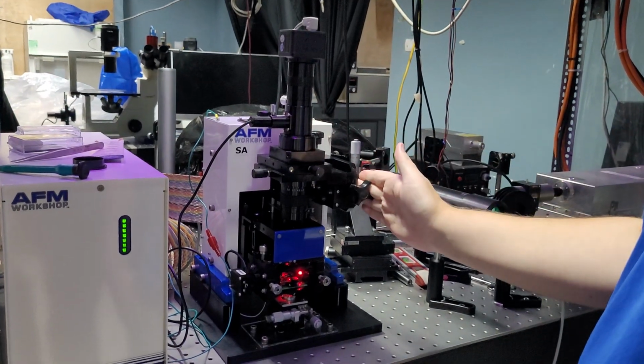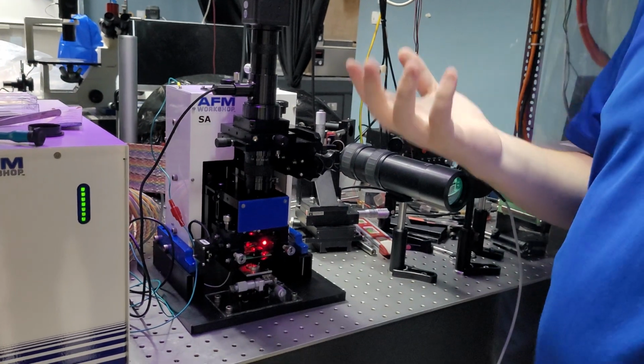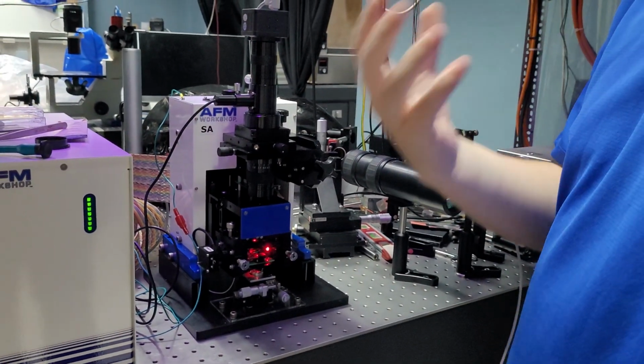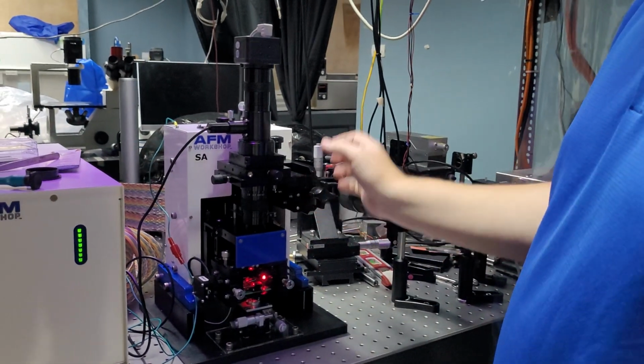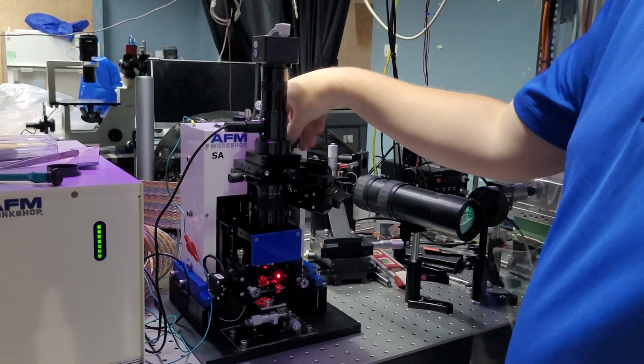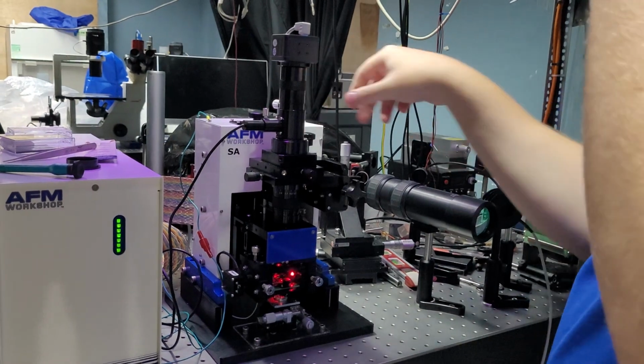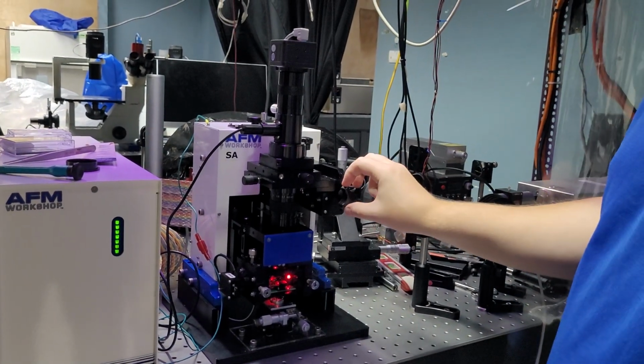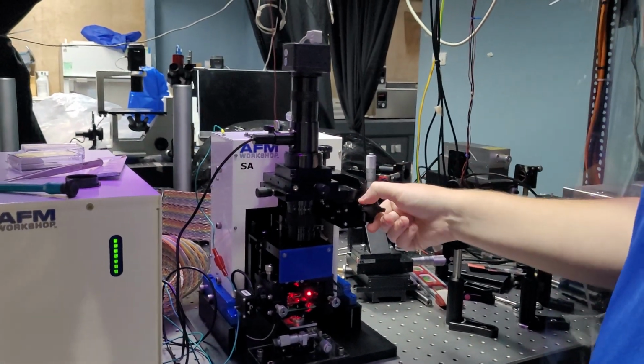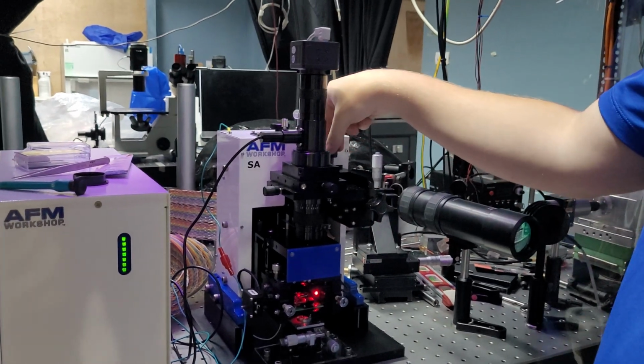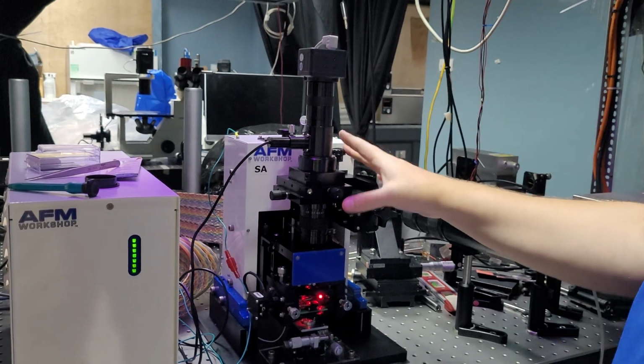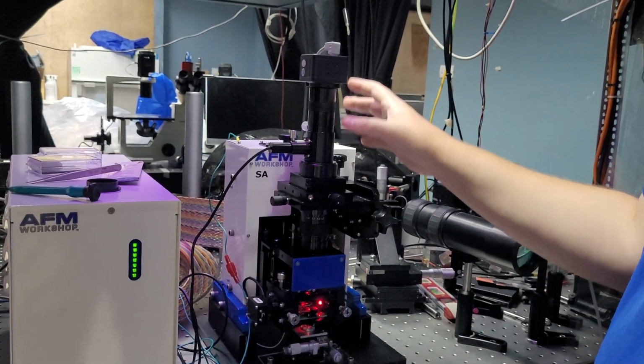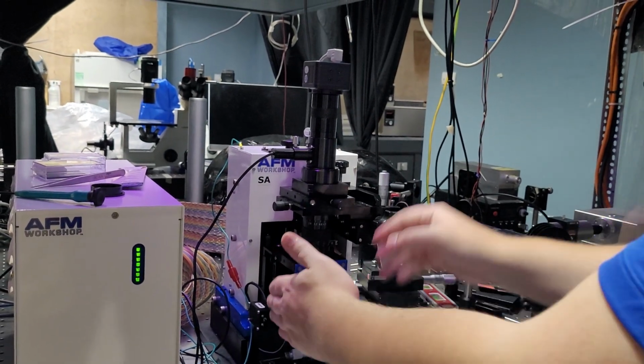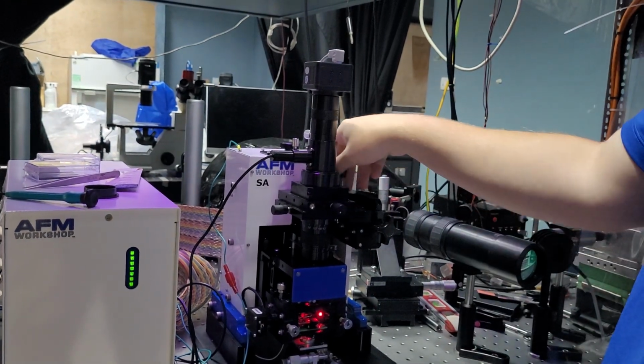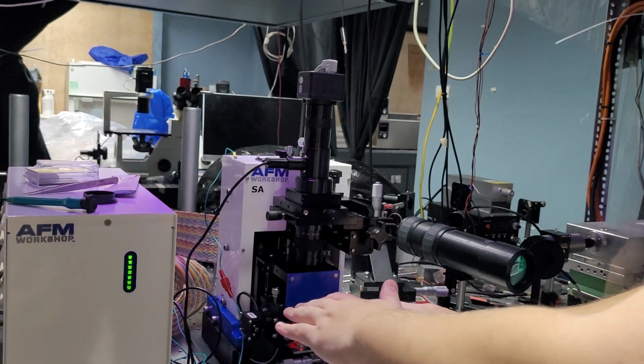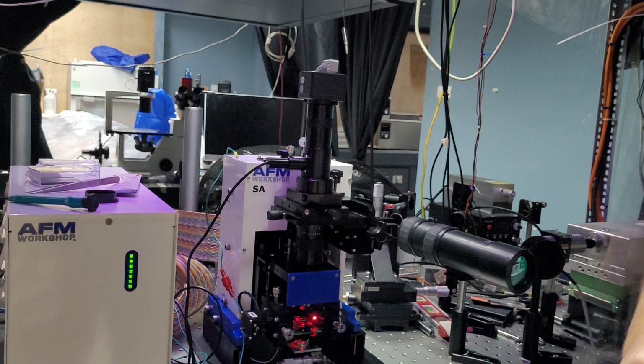Additionally, moving down a little bit more, you have a locking knob. Because this is a tip scanner, tip scanners are far more susceptible to ambient vibrations, causing issues with noise. One thing that you can do to help with that is, say for example, we are focused on our sample, then if we turn this knob here, what it does is it locks it in place so that it's no longer able to move. And then you can just give this a couple of turns the reverse way to disengage the optics from the rest of the microscope. So now, rather than the scanner having the light lever and the optics weight on it, you've reduced the load and the camera is completely removed from the scanner, so it's not going to add noise.